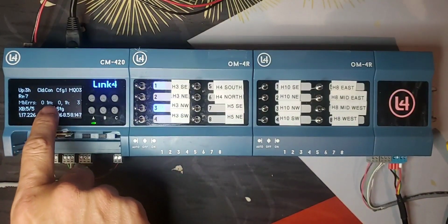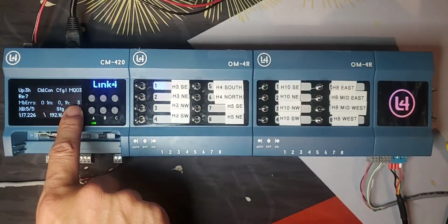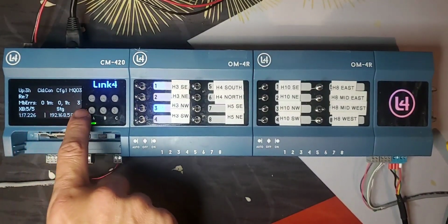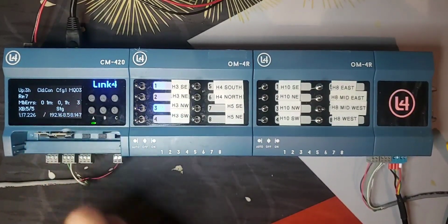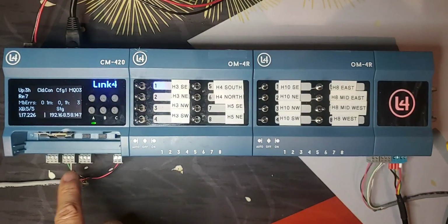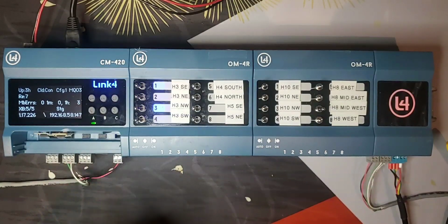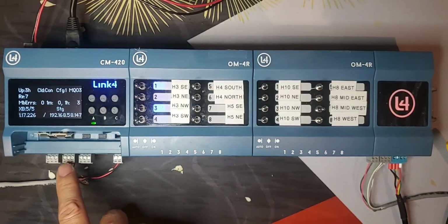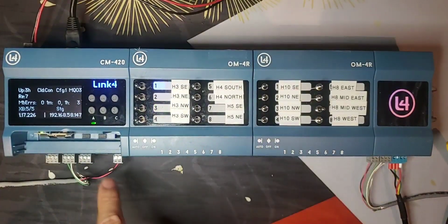But this count here and that count shows the number of errors you see in the bus. Typically, they all should be 0, right? So if you see some numbers on here, that means there's some kind of noise in the system. I would check the grounding, check the wiring, check any interference that affects the communication on the bus. Either could be this Modbus on COM2 or that Modbus on COM1. Everything can relate to it. These are Modbus errors, right? In the last hour, last minute.